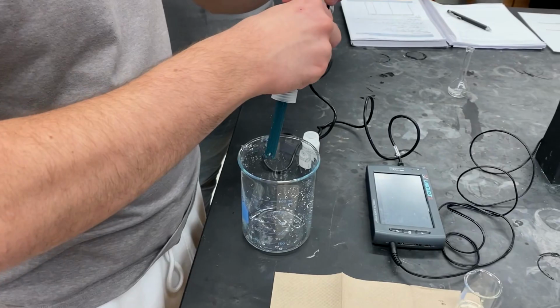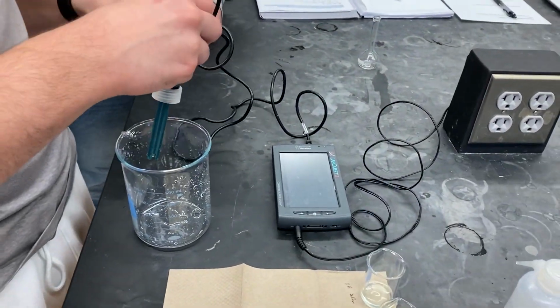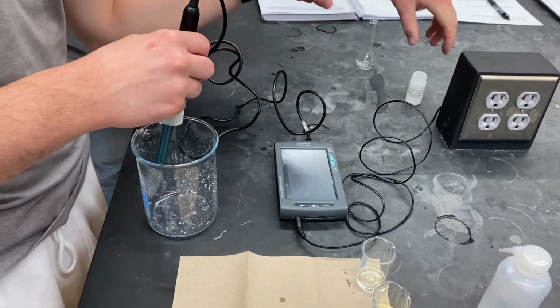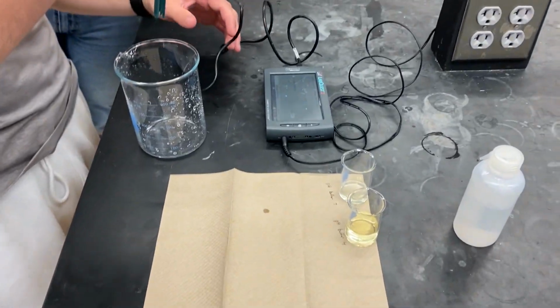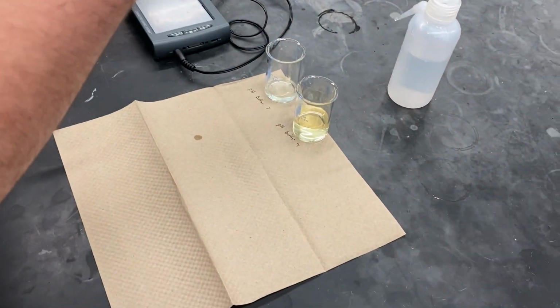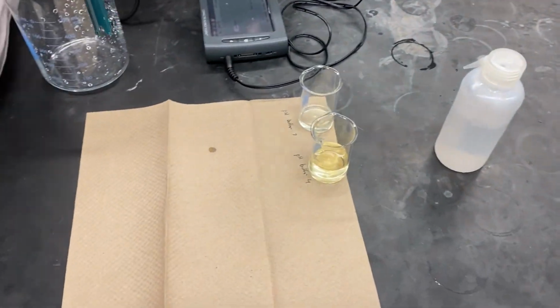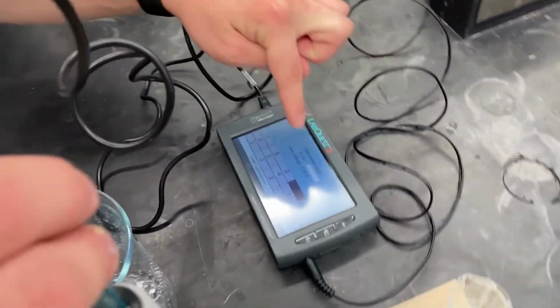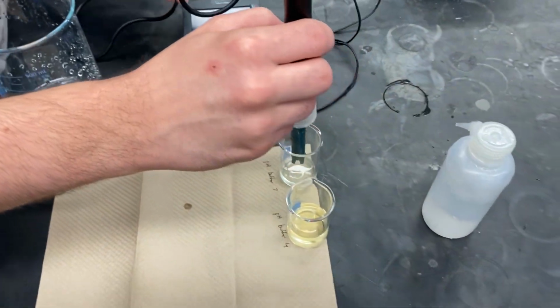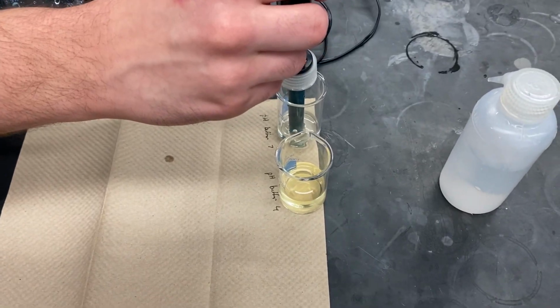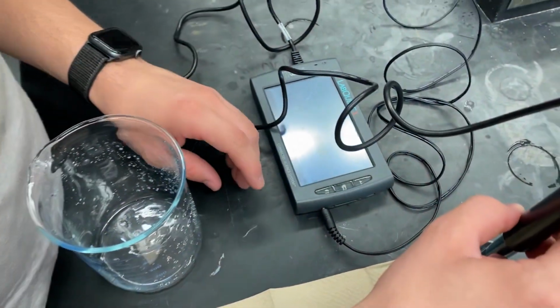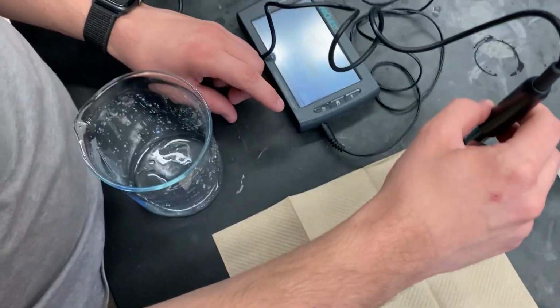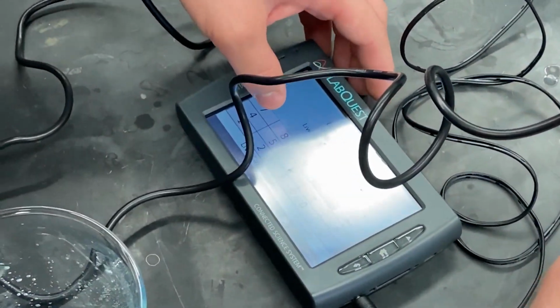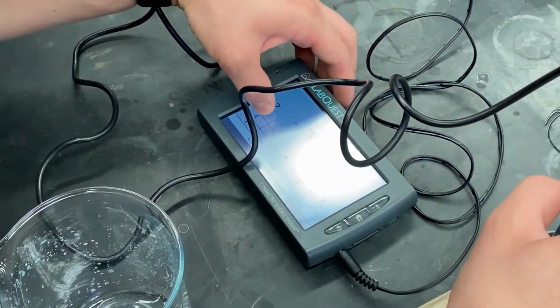The pH meter needs two buffers to be calibrated. We are using a pH 7 and a pH 4 buffer because we are using an acid. You'll want to use your pH 7 buffer first in your calibration. To start your calibration, dip your pH probe in the pH 7 buffer and wait for the voltage to stop changing. Then hit 7 and then keep.